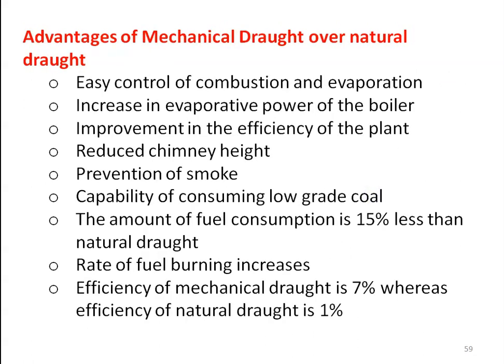Advantages of mechanical or fan draught system over natural draught system: easy control of combustion and evaporation; increases the evaporative power of the boiler — the amount of steam produced is increased; improves the thermal efficiency of the plant; reduces the chimney height; prevents black smoke; capability of consuming low-grade coal; fuel consumption is 15% less than natural draught; rate of fuel burning increases and heat generation also increases. The efficiency of mechanical draught is 7%, whereas efficiency of natural draught is only 1%. In modern high-pressure boilers, the balanced draught system is commonly used.